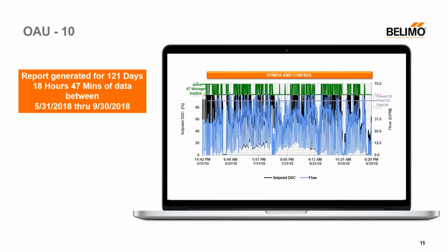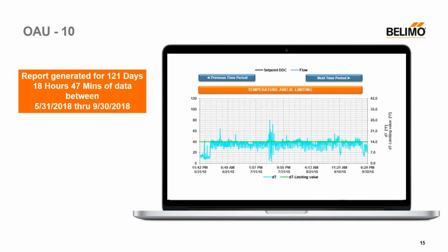And it's very interesting what we can do with these valves. We get an eye into the system and an eye into the point of heat exchange or energy consumption. We can really see what's going on with a particular unit. We can look at flows, we can look at the modes the valves are in, we can see what the valve was being commanded to do, as well as what the logic took over and actually did. So again, this one's May 31st through September 30th, roughly 2018, 122-ish days.